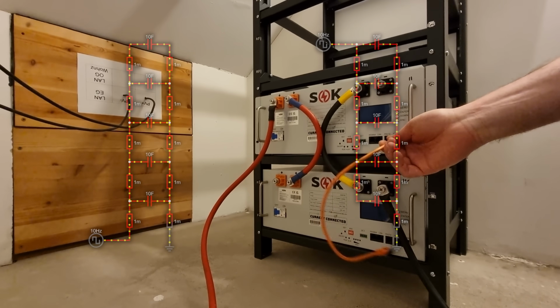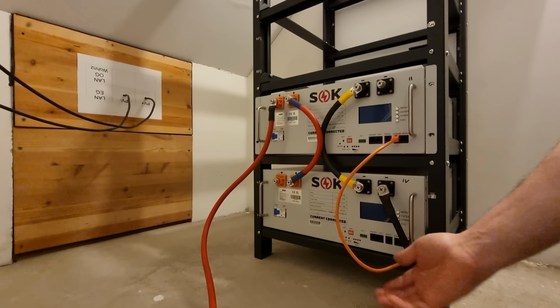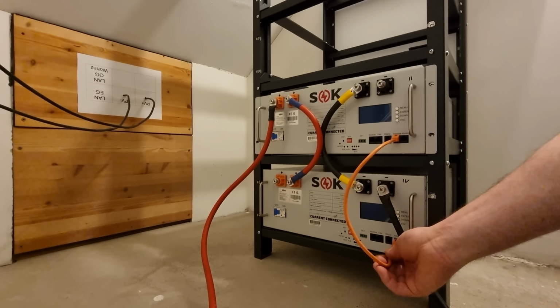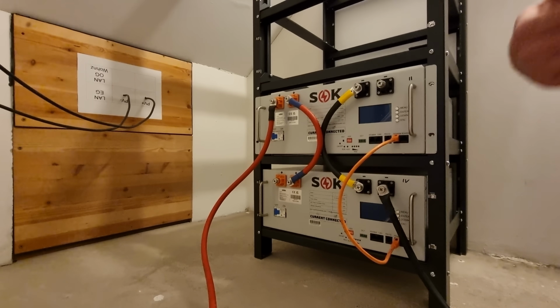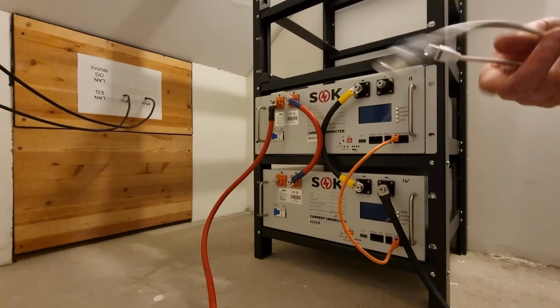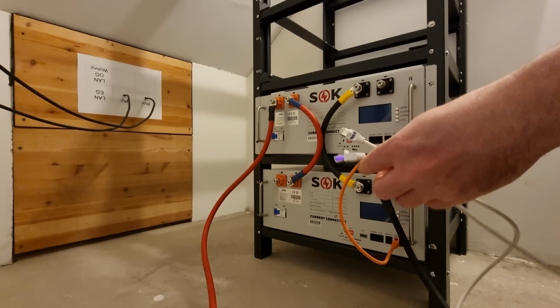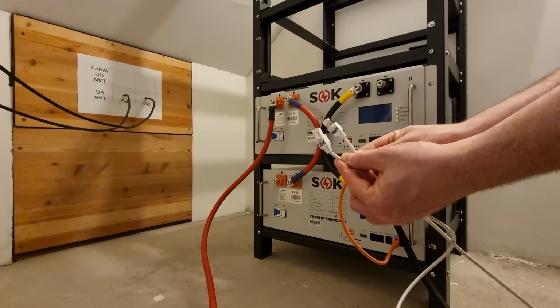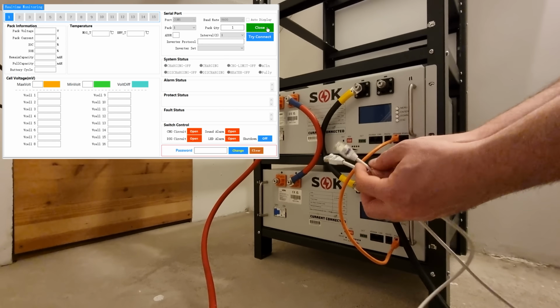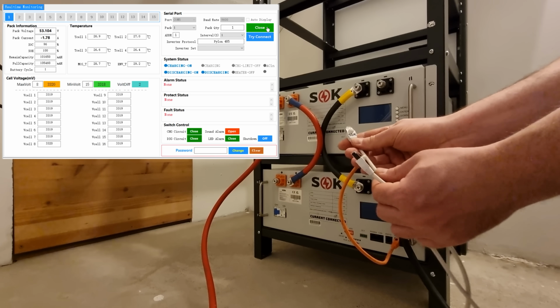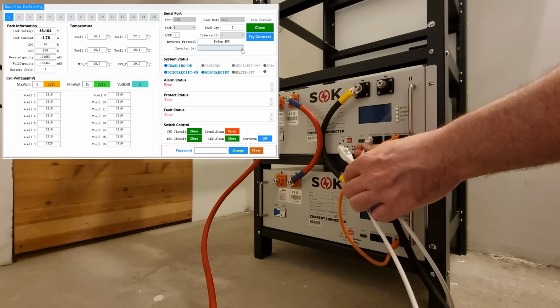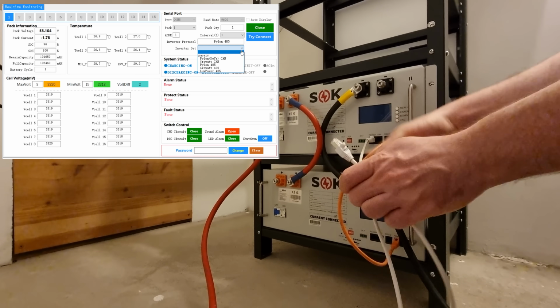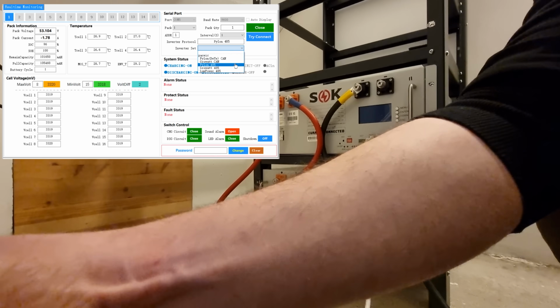For inter-battery communications, all it takes is a unique ID configured on each dip switch, and a series connection of all batteries through Ethernet cables. With a custom pinned cable, the first battery in an SOK stack can take control over the most popular charge controllers and inverters, such as Victron, Growatt, Sol-Ark, or the various Voltronic flavors, like my MPP Solar branded all-in-one box.